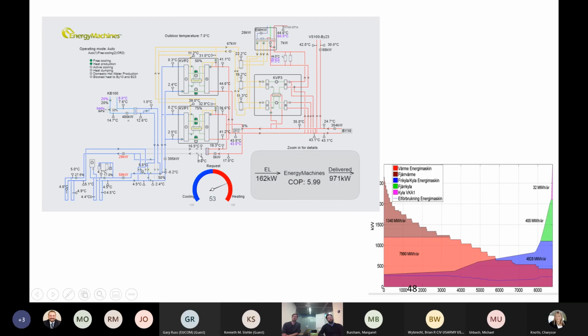Here you see the PI diagram of this. You've got 500 kilowatts of surplus heat coming in from the hospital. This is not even the coldest point, but on a winter night, minus 20 degrees, well below sub-zero Fahrenheit, you still get around 300 kilowatts of free heat coming into the system.